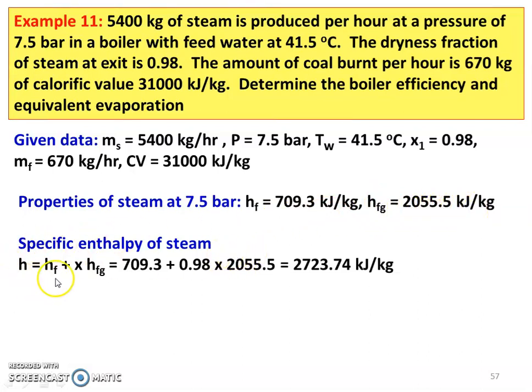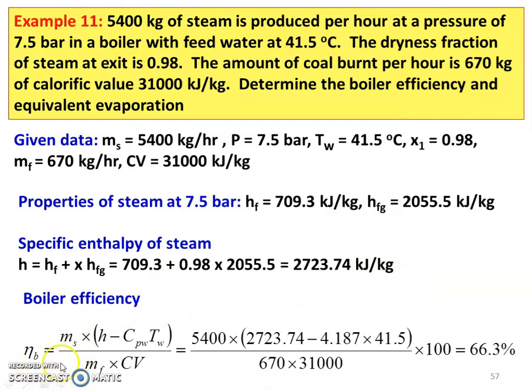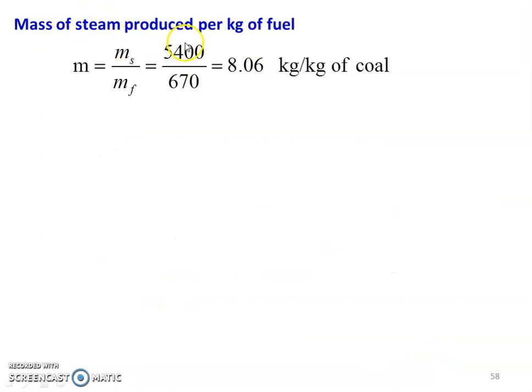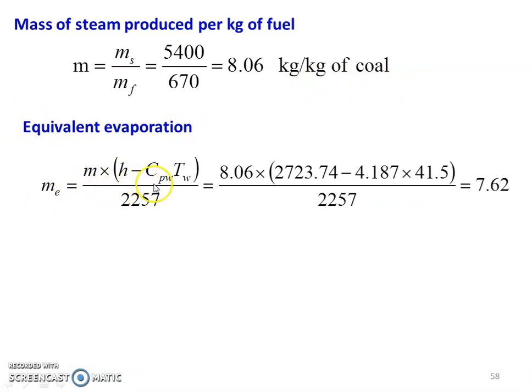The specific enthalpy of the steam: H equals hF plus x into hFG, which is 709.3 plus 0.98 into 2055.5, equal to 2723.74 kJ per kg. Boiler efficiency: eta B equals MS into (H minus Cpw into Tw) divided by MF into CV. So, 5,400 into (2723.74 minus 4.187 into 41.5) divided by 670 into 31,000, into 100, equals 66.3%. Mass of steam produced per kg of fuel: M equals MS divided by MF equals 5,400 divided by 670 equals 8.06 kg per kg of coal. Equivalent evaporation: ME equals M into (H minus Cpw into Tw) divided by 2257, which is 8.06 into (2723.74 minus 4.187 into 41.5) divided by 2257, equal to 7.62 kg per kg of coal.